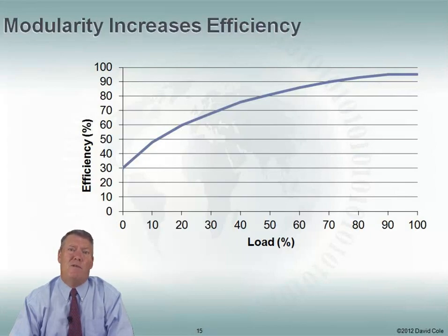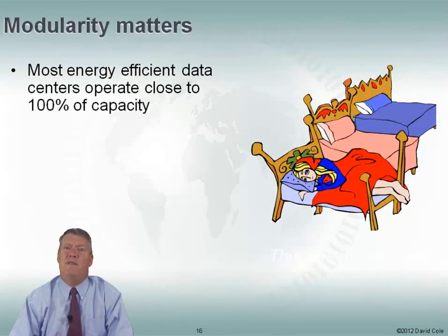Most of the time in the data center, if we look at a server, we might be using only 6 to 10% of it, so we're very lightly loaded, and we'll also have very poor efficiency on that server. Let's look at a UPS: a typical UPS might be 30% loaded. If I could take that same UPS and load it to 50 or 60%, it would be much more energy efficient. Same thing applies to power supplies, UPSs, PDUs, and cooling units—the more I load these up, the more energy efficient they become. That's why modularity matters; it's very important.